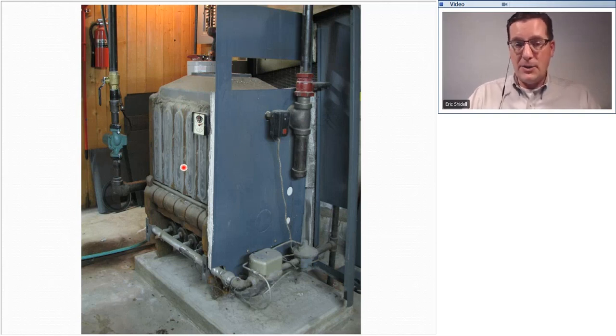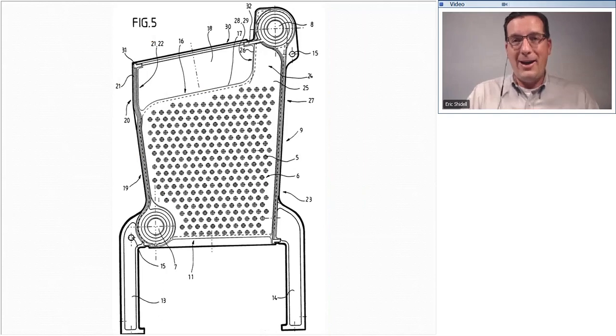It is possible to tear this cast iron boiler down and reseal that heat exchanger. But that's not something that would be my first choice, because this thing is old enough. Now, a second thing to think about with these old boilers. Here's an old patent diagram from a cast iron section. One of the problems that old cast iron boilers can experience is an accumulation of sludge down in the bottom of the heat exchanger section. I'll draw a little line on the bottom there. It's kind of hard to see, but there's a little line right there. It's almost like a mud.